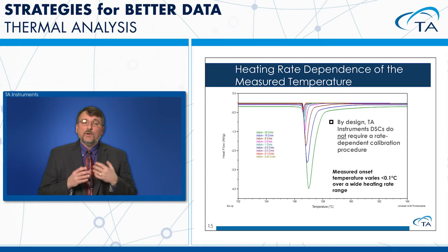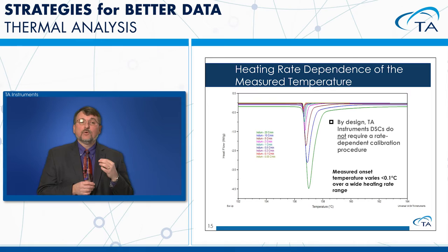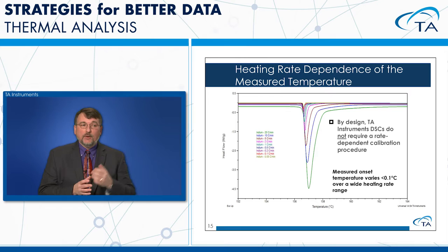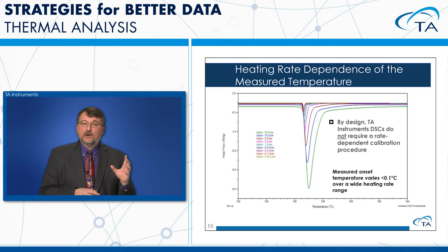In our DSC cells, rate-dependent calibration is not necessary. By design, TA Instruments DSCs do not require a rate-dependent calibration procedure. Here's data where we ran indium from 0.05 to 20 degrees per minute. Plotting all nine runs, the melting onset varies by only 0.1°C over that wide range of heating rates — a very small change, confirming no need to change calibration for different heating rates.